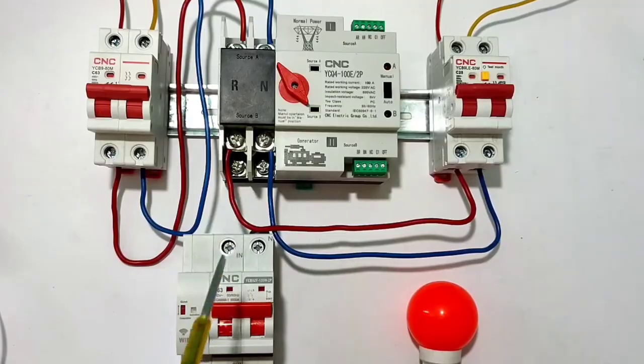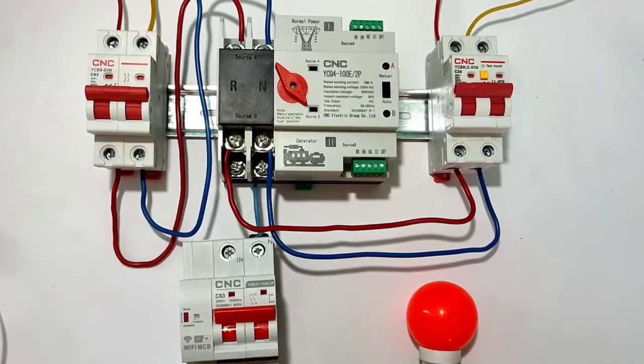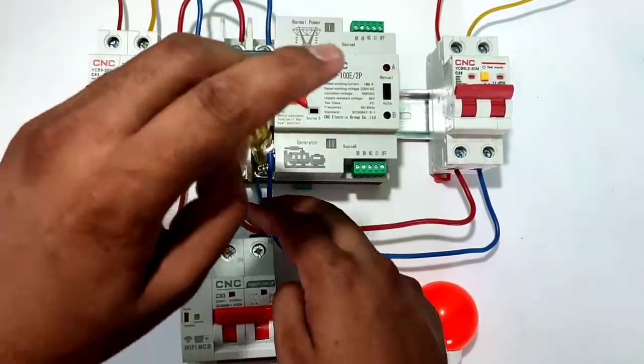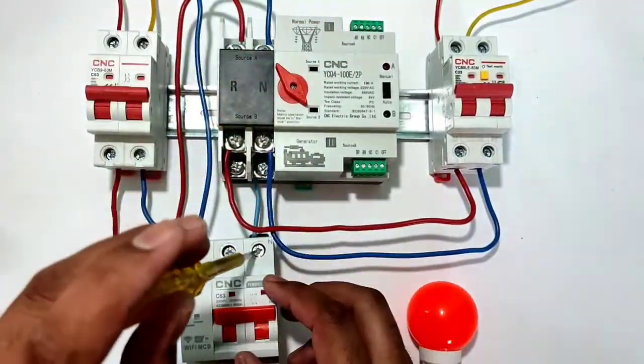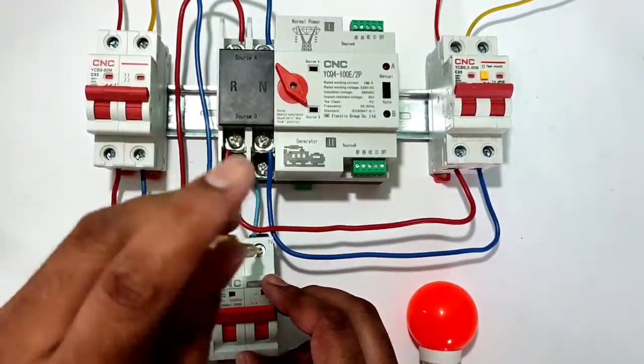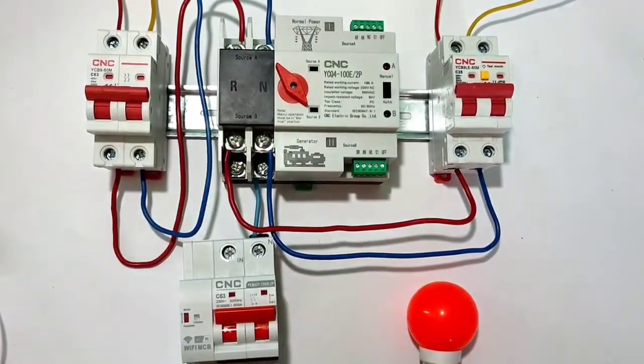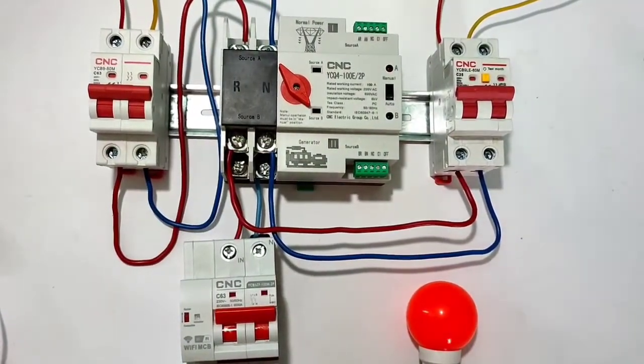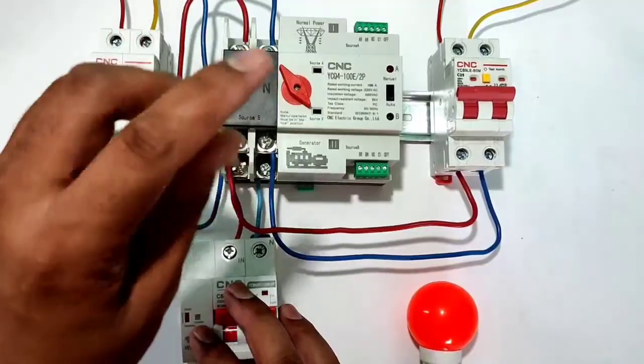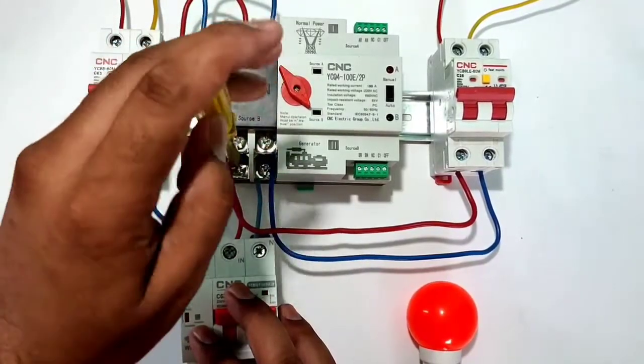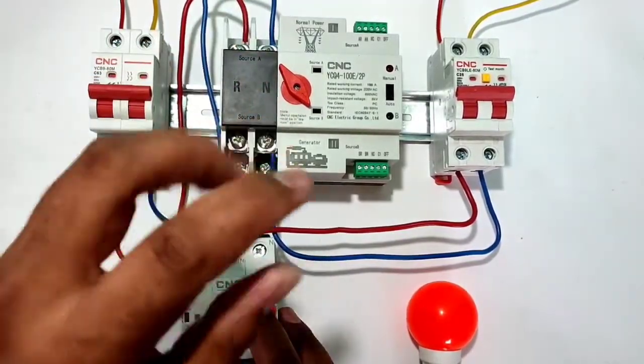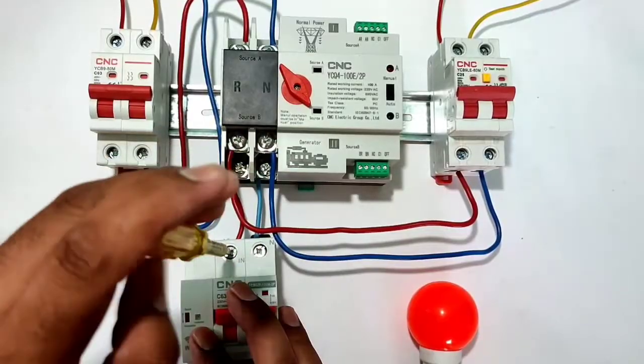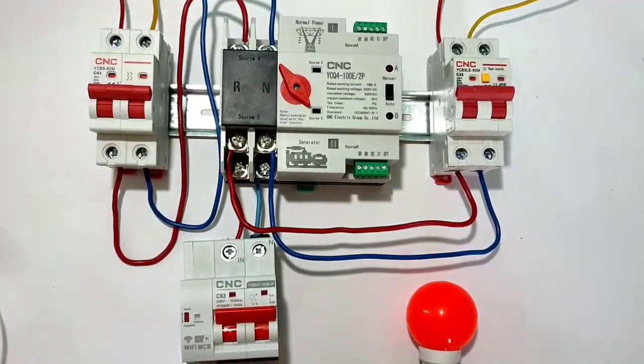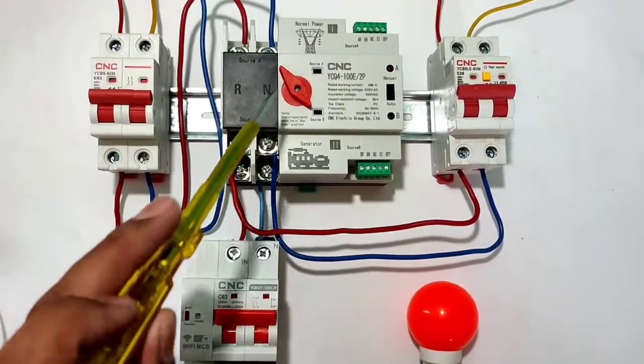Now we connect the output wire. So we connect a neutral wire. You can see here the automatic transfer switch neutral wire connects here to the load MCB neutral terminal. Okay, so the output neutral connection is done. Same connection for the phase wire: the automatic transfer switch phase wire connects here to the load MCB phase terminal. You can see here. Now the automatic transfer switch power wiring is done.